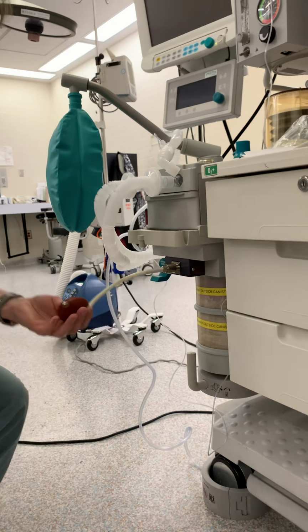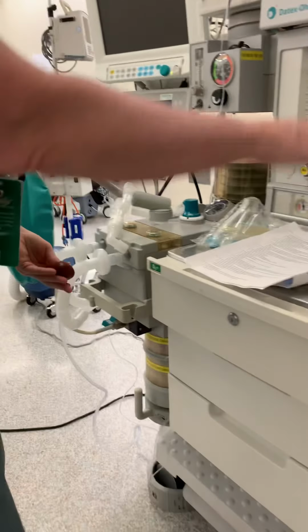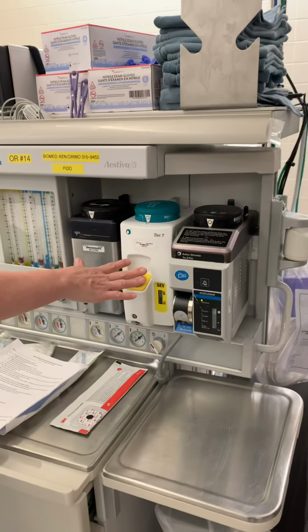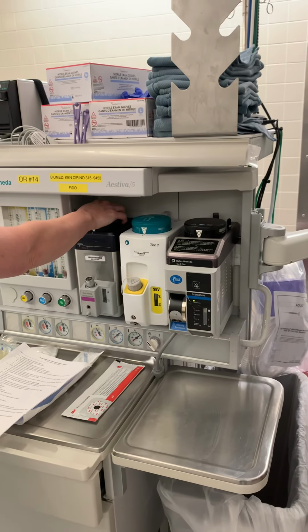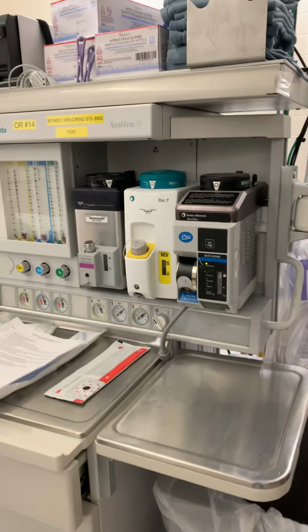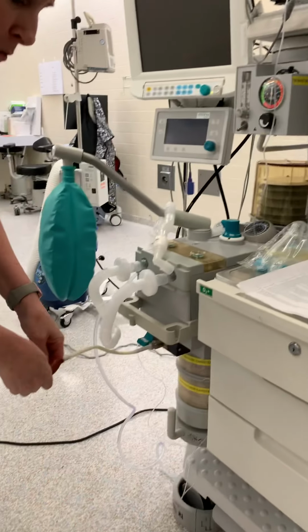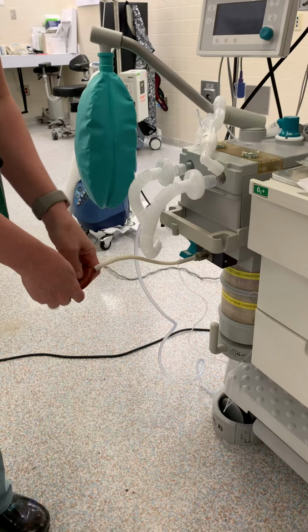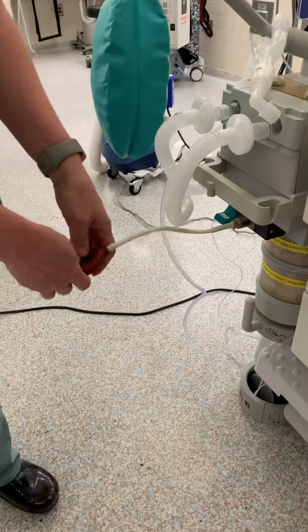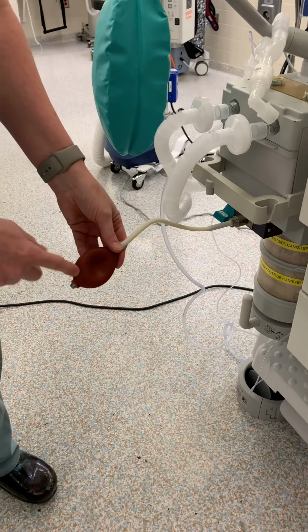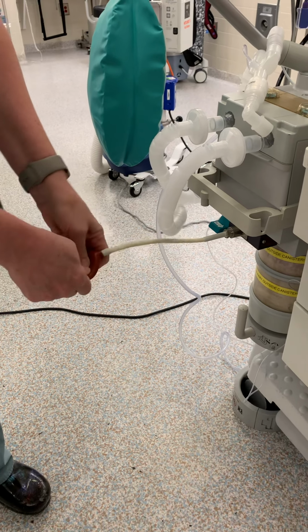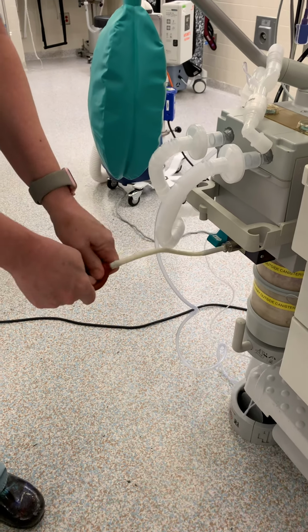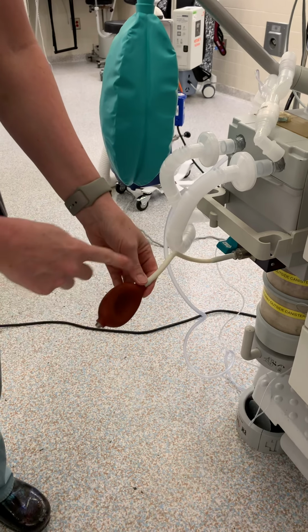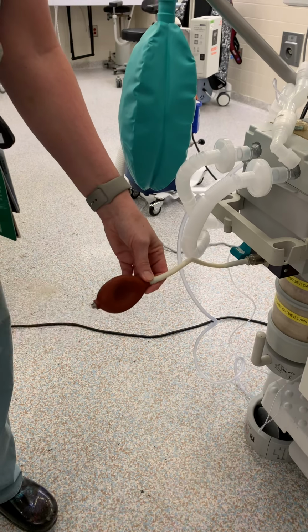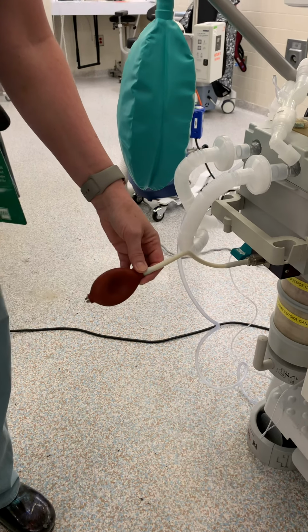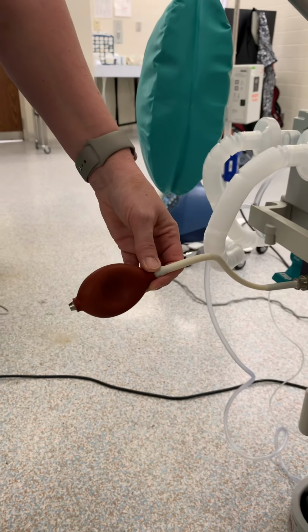While we still have the bulb in place, we also want to make sure there's no low pressure leaks in your vaporizers, and you'll do that by just cracking on a vaporizer. Your bulb will fill with air. You just need to depress it again, getting all the air out, and just make sure that it remains depressed. If it fills back up immediately, just keep deflating it until you can make sure you got most of the air out. And as long as it holds a depression, it's passed the test.